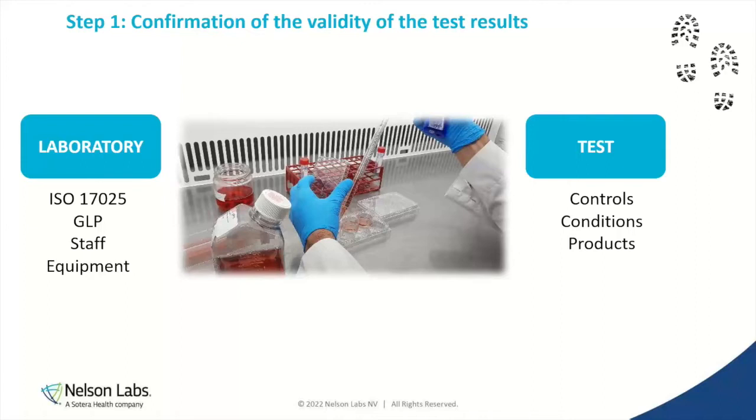So what you're going to do is look at the report you have received, and you're going to see, okay, does this data make sense? How can you check it? You check, okay, what lab facility did it? Is it accredited? Is the test accredited according to ISO 17025 or under GLP? Was the staff trained? Was the equipment qualified? You look at the test controls. Were they okay? What were the conditions? And so on. Was there expired product used? These are all very important questions.